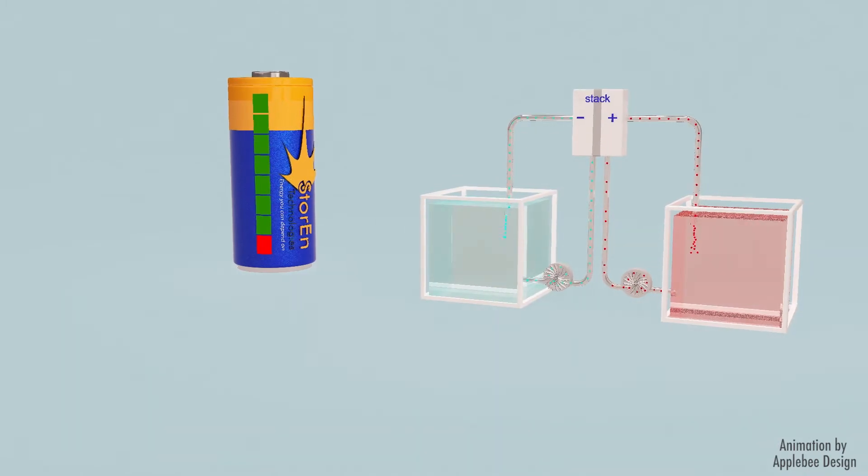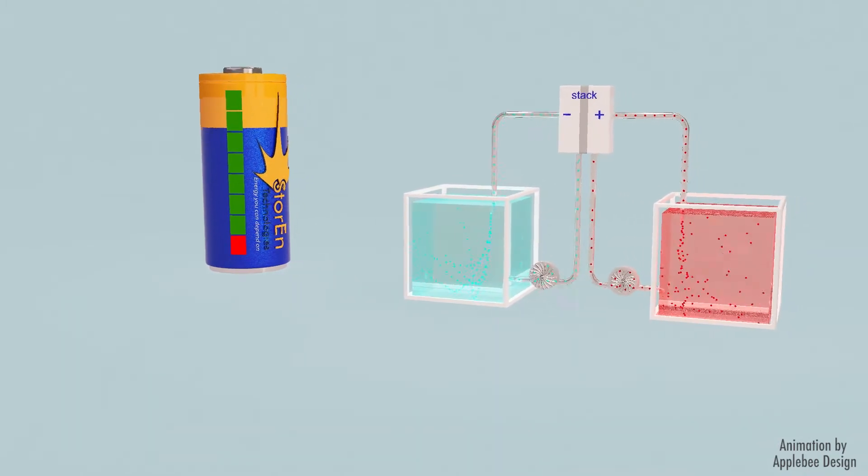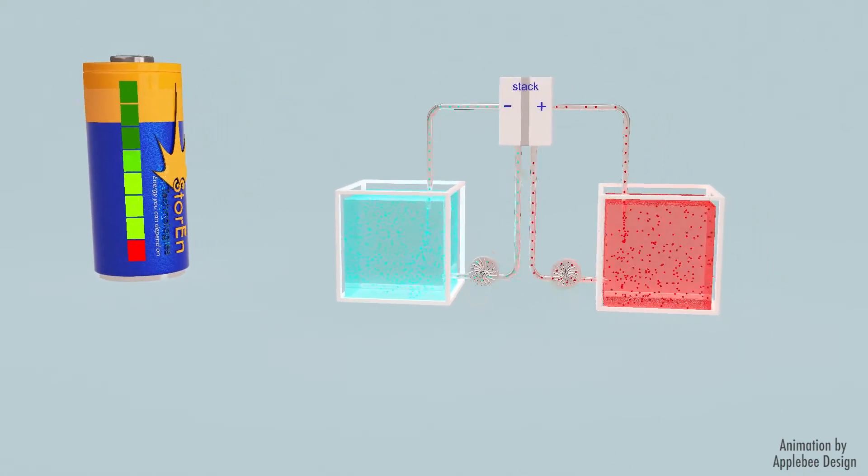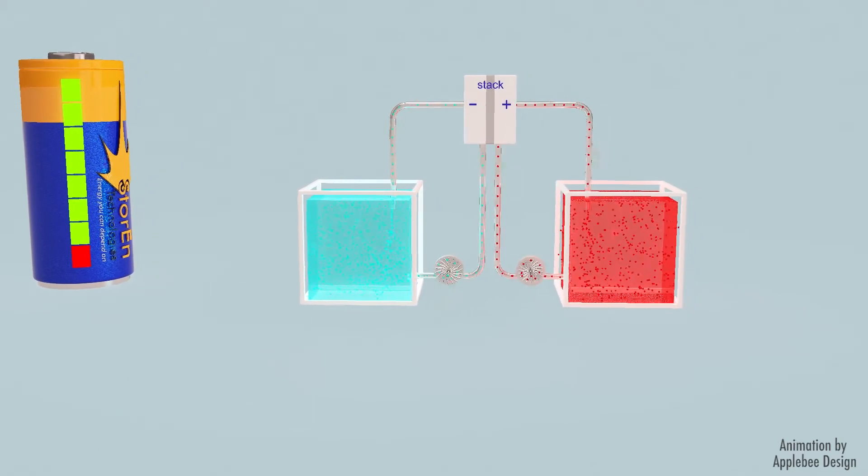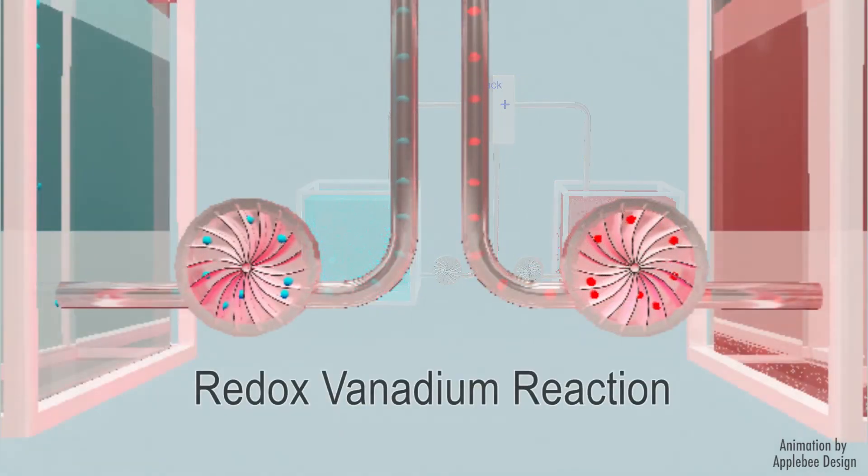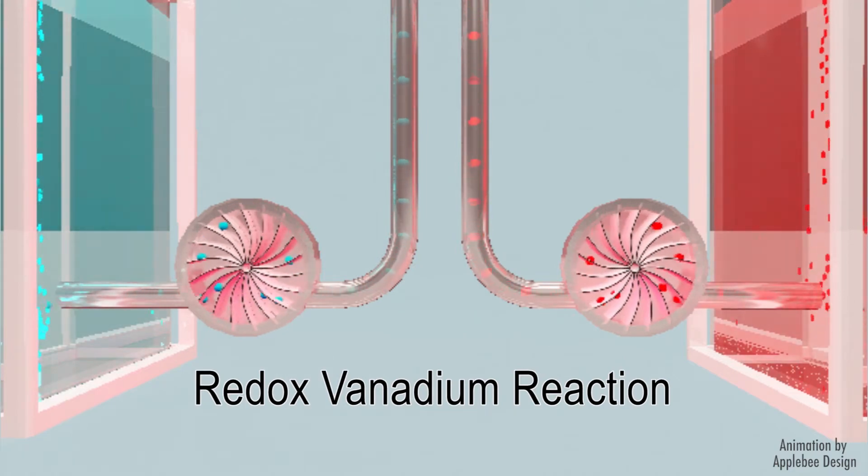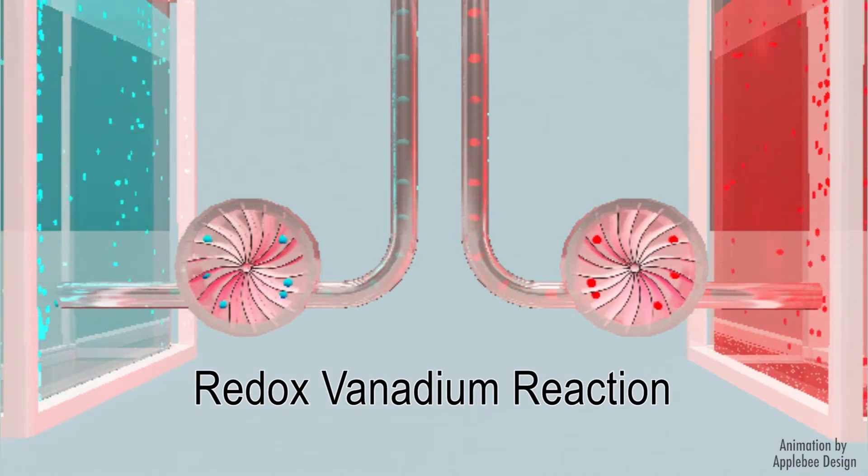In a vanadium flow battery we find two tanks of electrolyte solution, one positive and one negative, with a charging-discharging cell stack between them. Two pumps make the negative electrolytes and the positive electrolytes flow through the cell stack, where a thin proton exchange membrane prevents the two electrolyte solutions from mixing together.